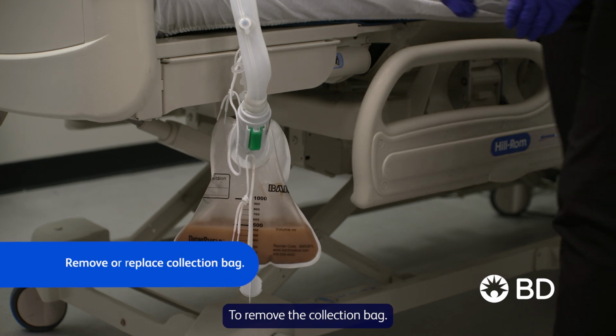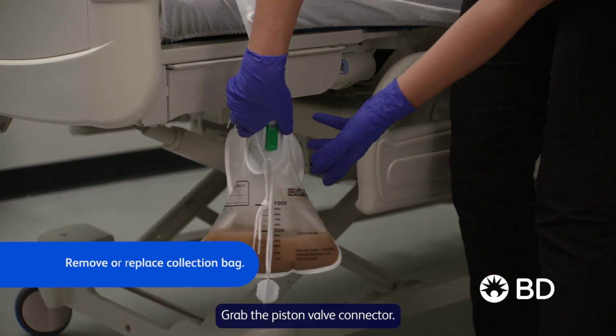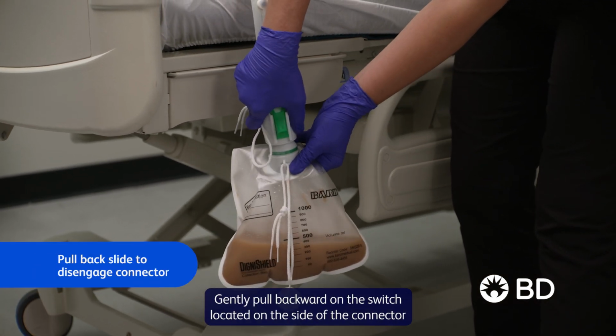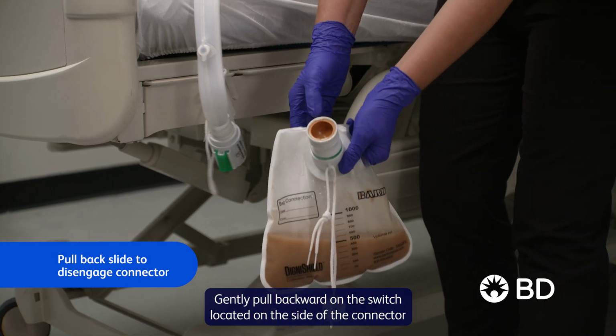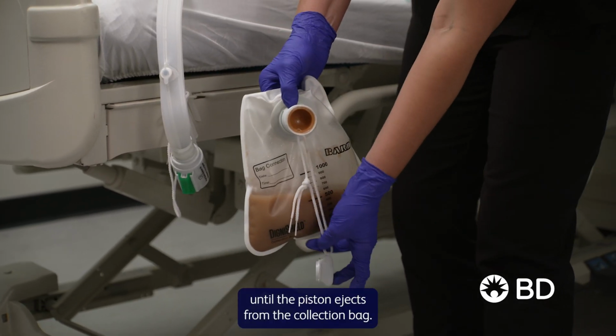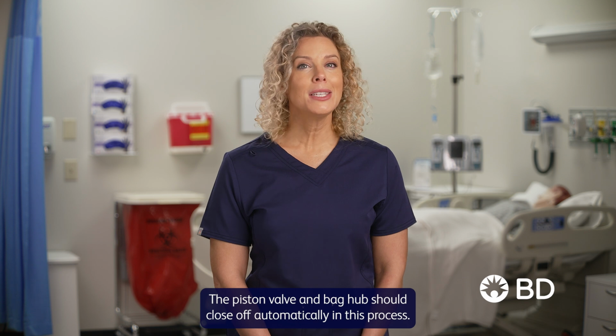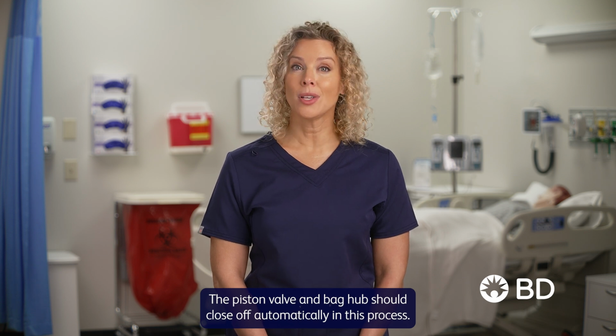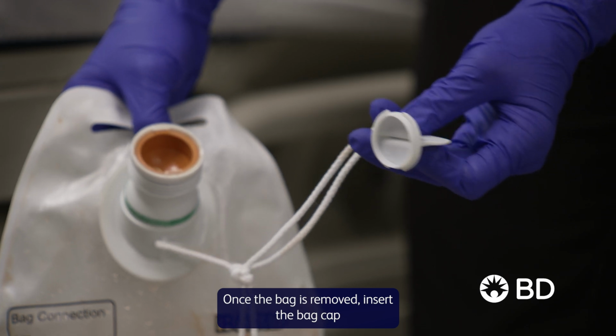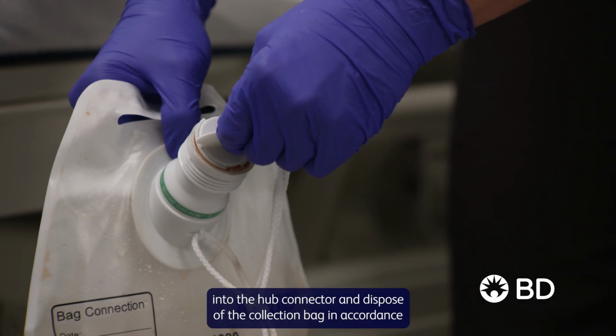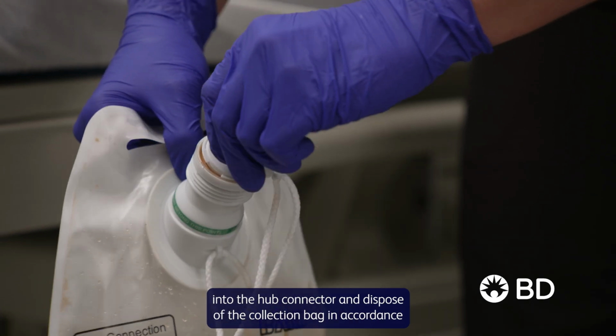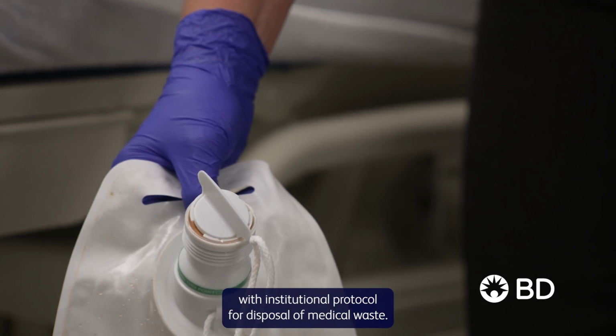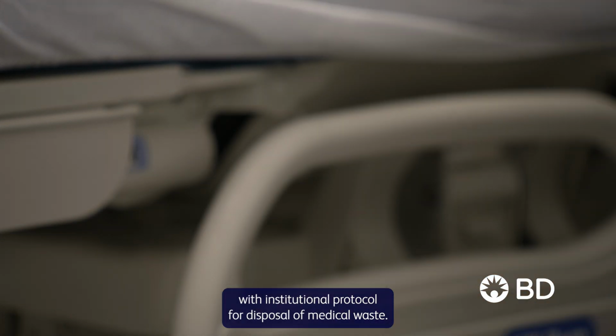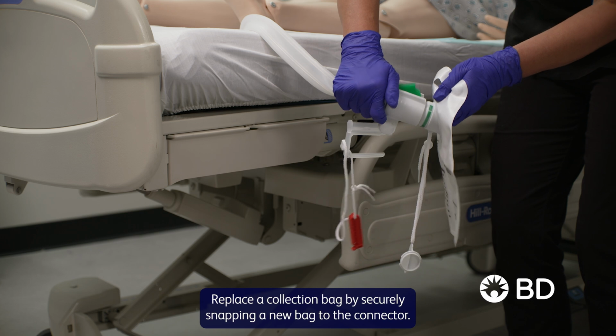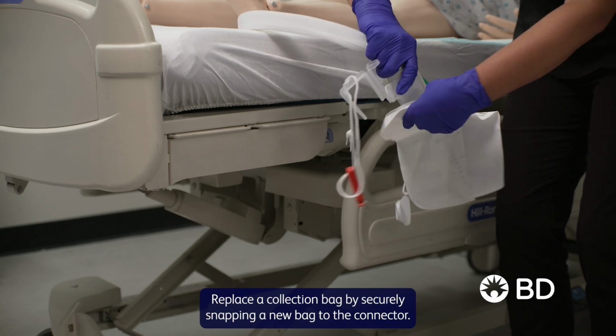To remove the collection bag, grab the piston valve connector, gently pull backward on the switch located on the side of the connector until the piston ejects from the collection bag. The piston valve and bag hub should close off automatically in this process. Once the bag is removed, insert the bag cap into the hub connector and dispose of the collection bag in accordance with institutional protocol for disposal of medical waste. Replace the collection bag by securely snapping a new bag to the connector.